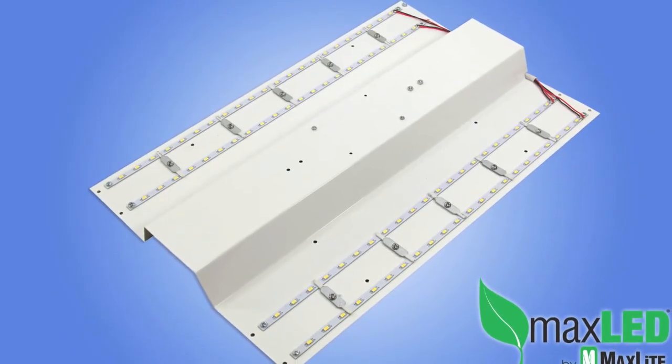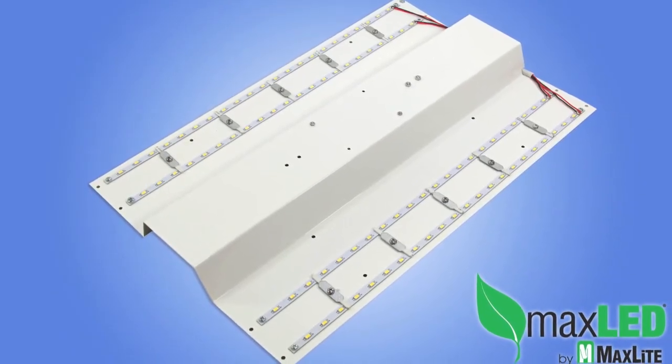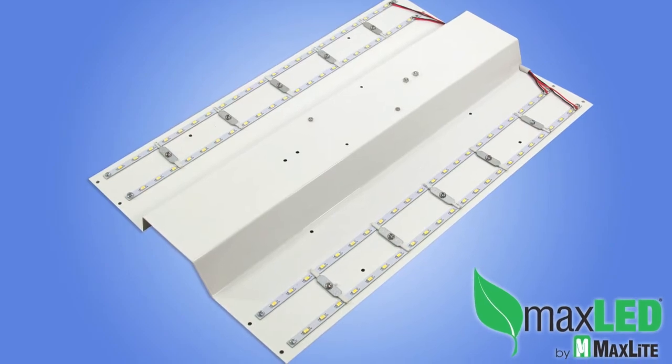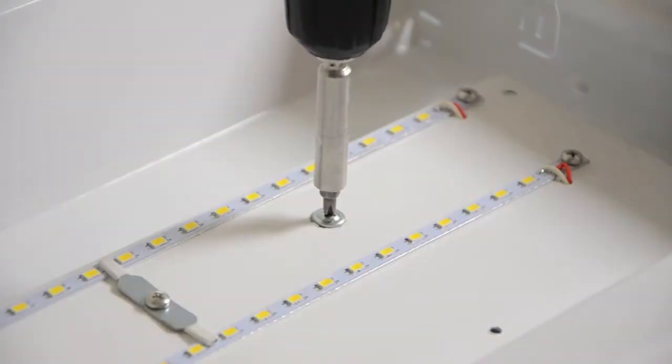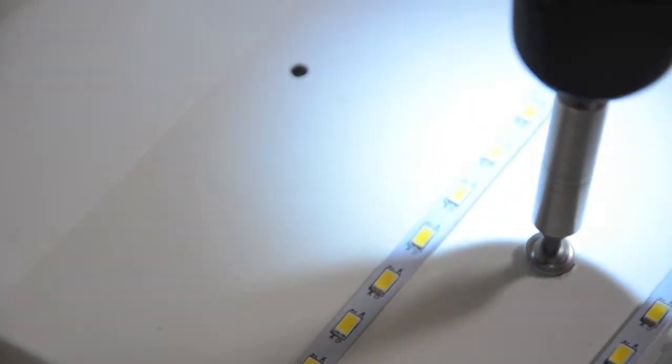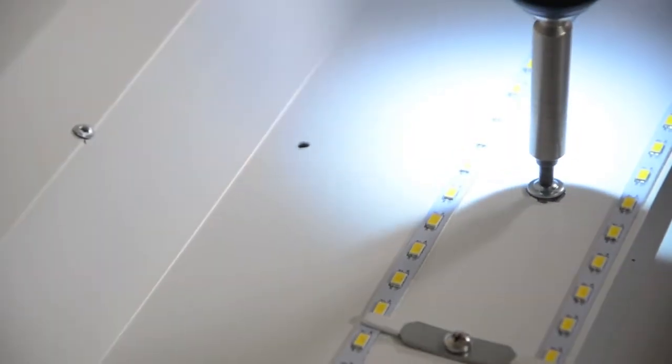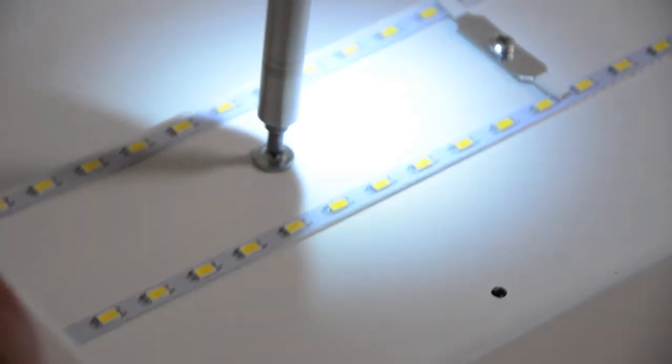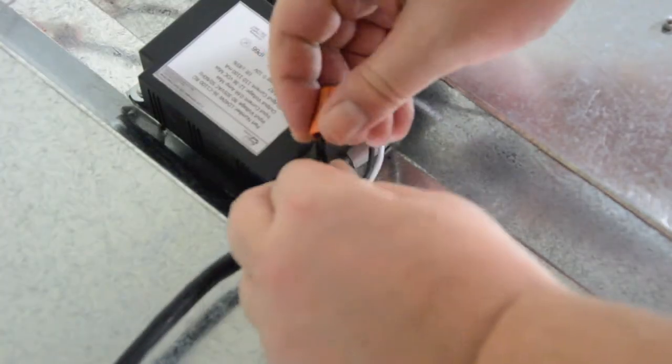Now the MaxLite Batwing Retrofit Kit is ready to mount. Carefully hold the kit square with the fixture and in the center. Screw the first corner self-drilling screw until it penetrates and pulls the kit up into the fixture. Do the same in the opposite corner. Now the fixture will hold in place while you do the same for the remaining screws.